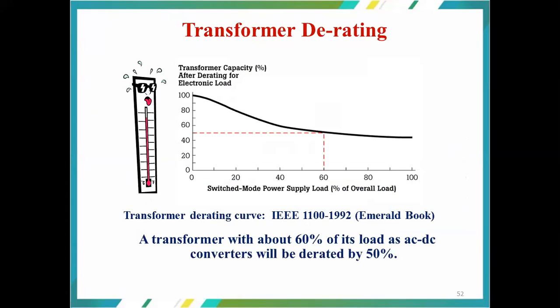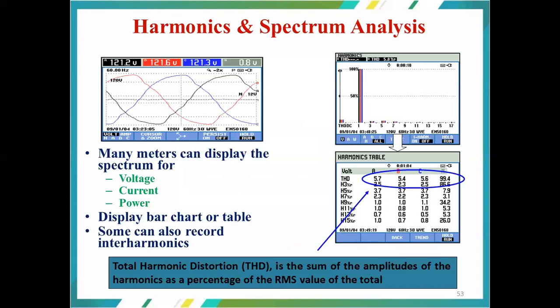That means if a 100 kVA transformer is connected to a particular facility, and 60% of the connected load, assume it is charging stations, then the transformer rating is going to get derated to 50 kVA. So again, the transformer derating curve is given by the IEEE 1992 standard. The curve is as shown.